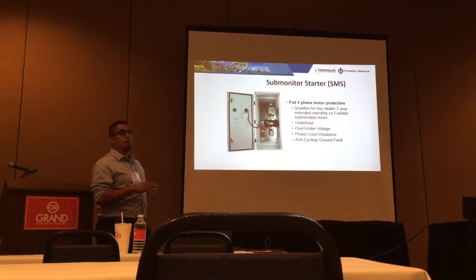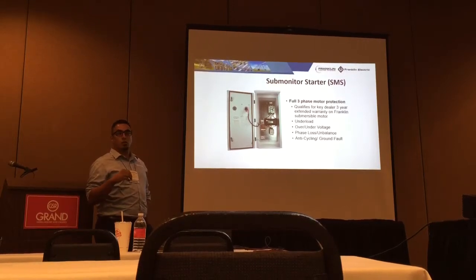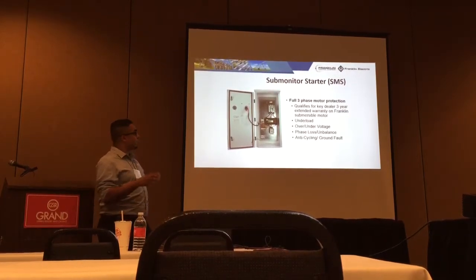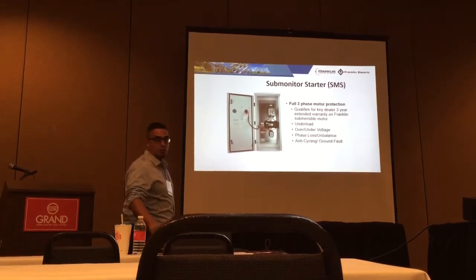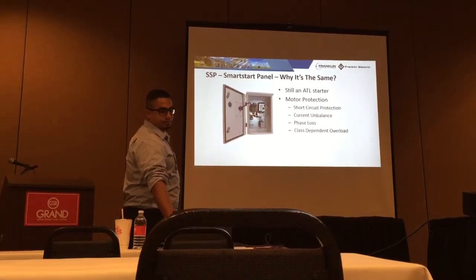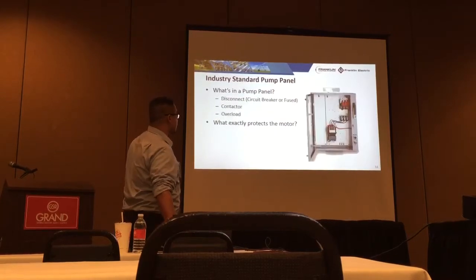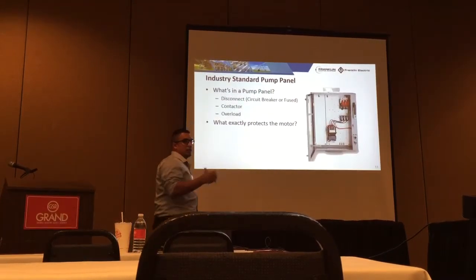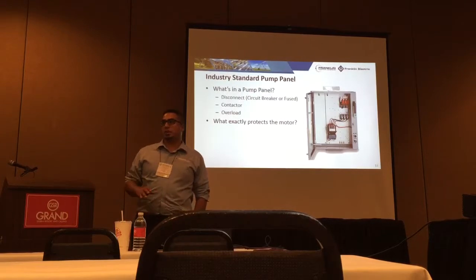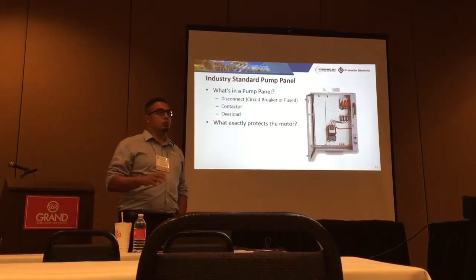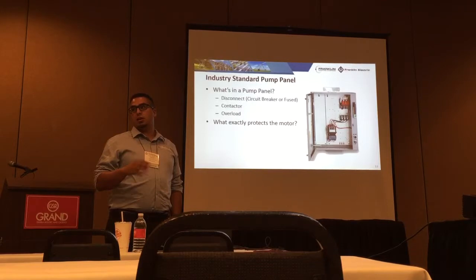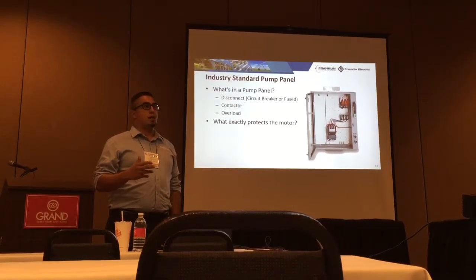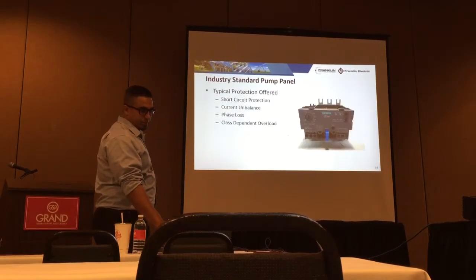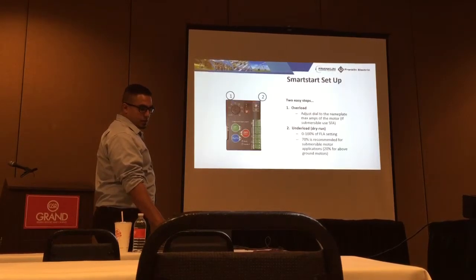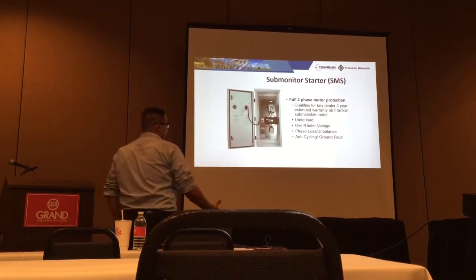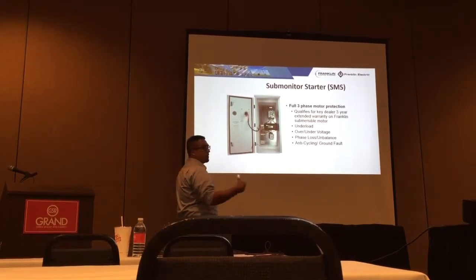So this was Franklin Electric's in-house engineered overload that you could drop into any panel. You could drop it into one of these panels in place of the ESP and have fully adjustable 3-phase protection: underload, overload, over voltage, under voltage, current trips, ground faults, all resettable with times.